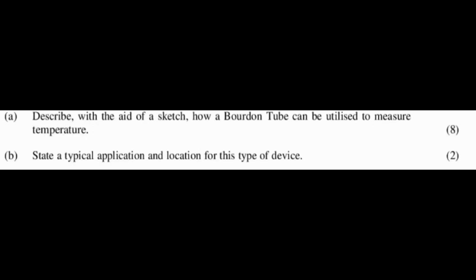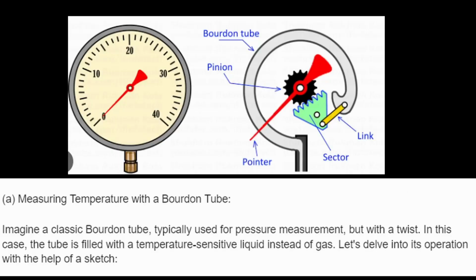Describe, with the aid of a sketch, how a Bourdon tube can be utilized to measure temperature. B. State a typical application and location for this type of device. Measuring temperature with a Bourdon tube. Imagine a classic Bourdon tube typically used for pressure measurement, but in this case the tube is filled with a temperature-sensitive liquid instead of gas. Let's delve into its operation with the aid of a sketch.